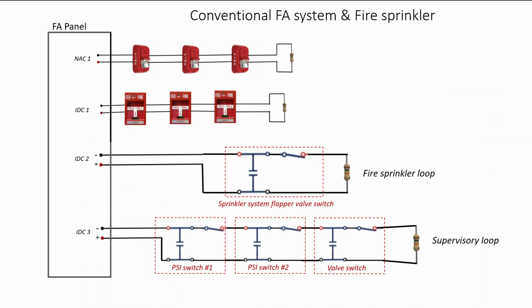So here we can see an example of the entire system to a Class B conventional. This loop here is the fire sprinkler loop, where we have a fire sprinkler flapper valve. That would be for a dry system, and it has a tamper switch in it. Not every flapper valve will have a tamper switch, but some will, so we're going to include it in this diagram. Down here, these are all supervisory devices. These are all pressure switches, and maybe they're connected to valves to see if the valve has been opened. Each of those will have a tamper switch.